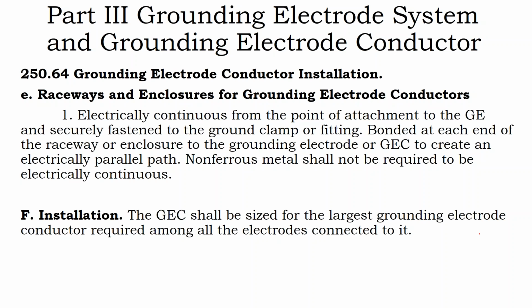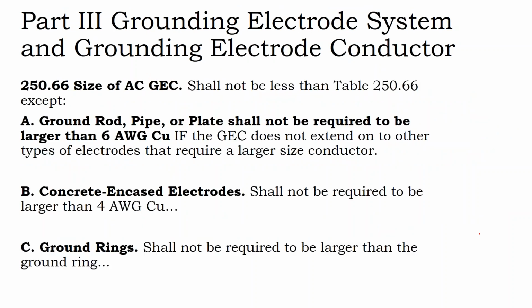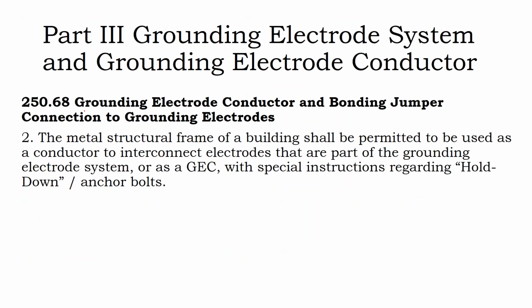Let's see. There's sizing requirements. Table 250.66. What's common on a grounding electrode system is to run bare number 6 up to the rooftop. If you want to put it in a green sheathing, you're allowed to. It doesn't have to be bare. It can be insulated.